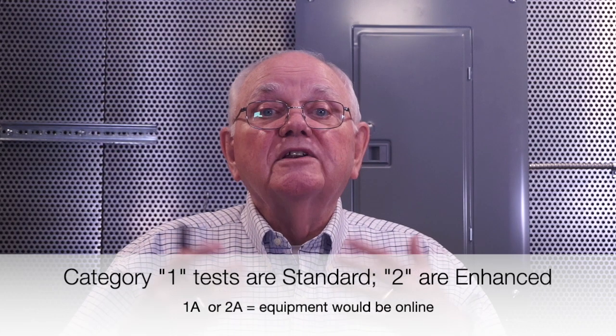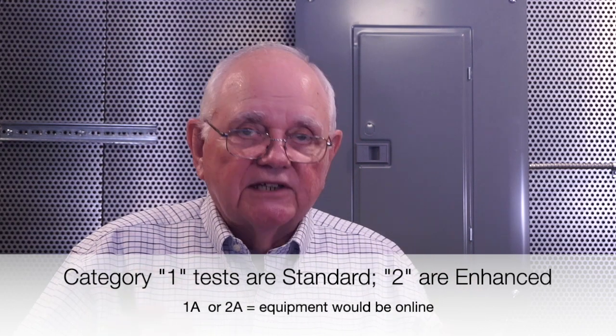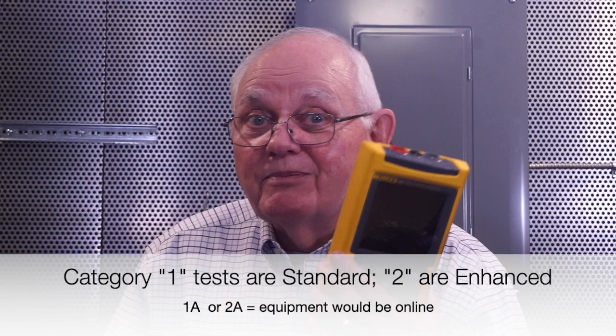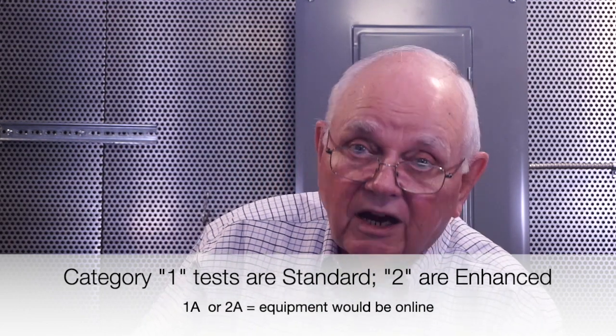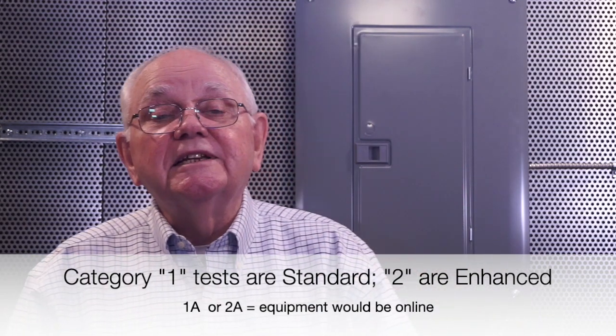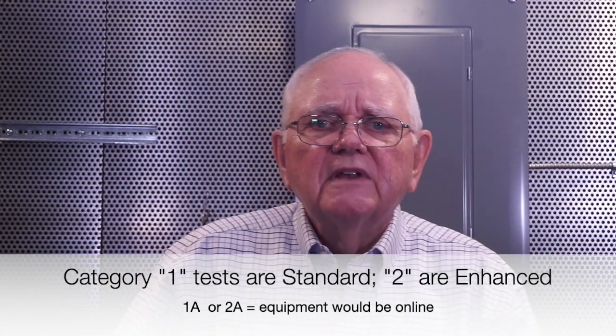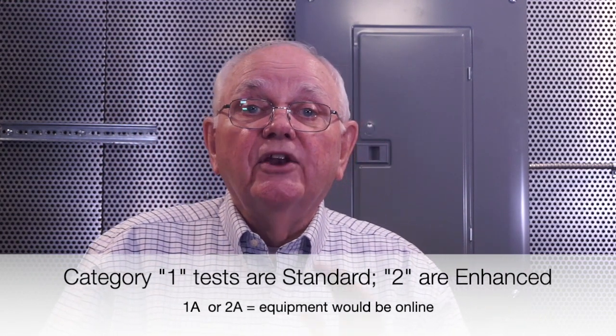Whereas a Category 2 test is a more enhanced test where, maybe we need to go to the power quality analyzer, the high pot, or the polarization index test, whatever it is. We've got to know those tests, know how to conduct them, and how to interpret their results as well. That's only about the first 4 chapters or so in NFPA 70B.